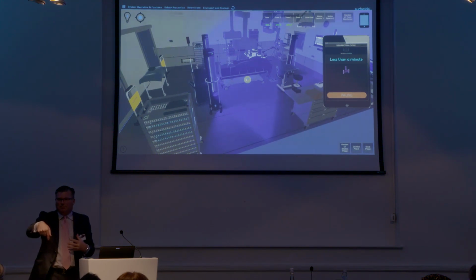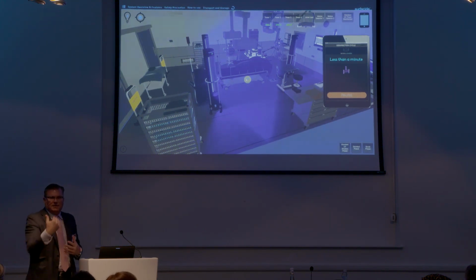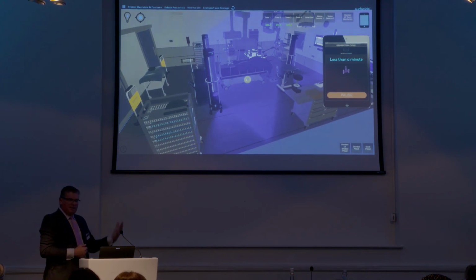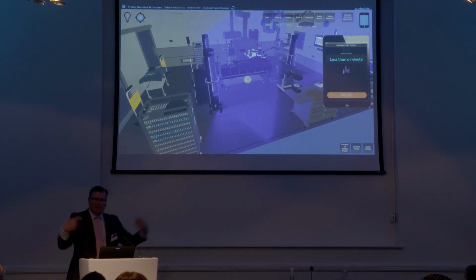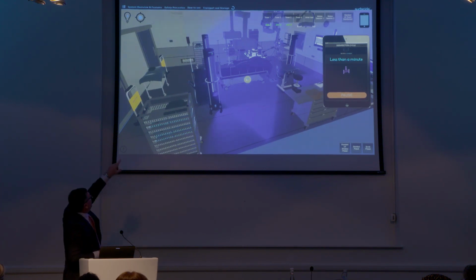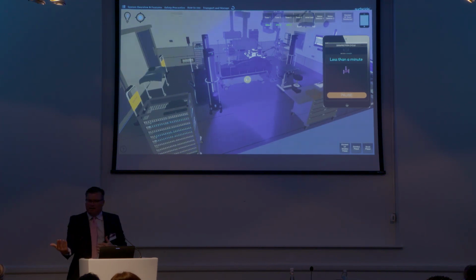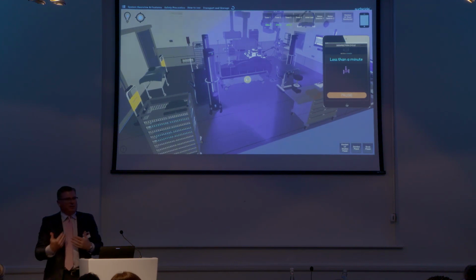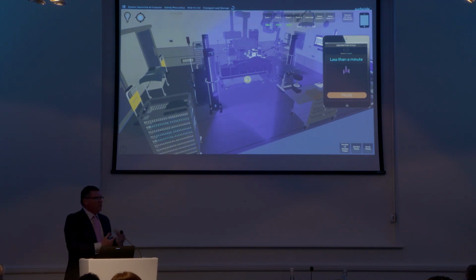If we were just in one position, we would be blocked and the energy would not have access to many of the high-touch surfaces. But by having 3 of them, we're coming from more angles to be able to do that. The tablet remains outside the room, so we can see it outside of the door. There would be a standard caution sign with the tablet, and the cycle countdown is always available, and you always know when the room will be ready for occupancy at the termination of the cycle.